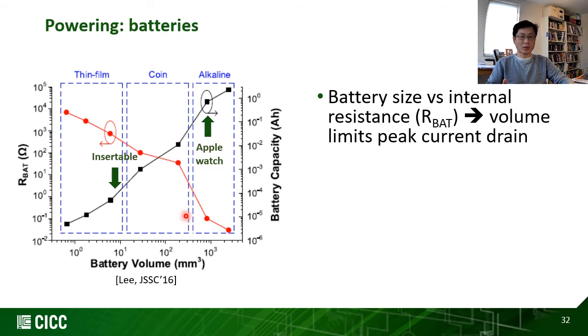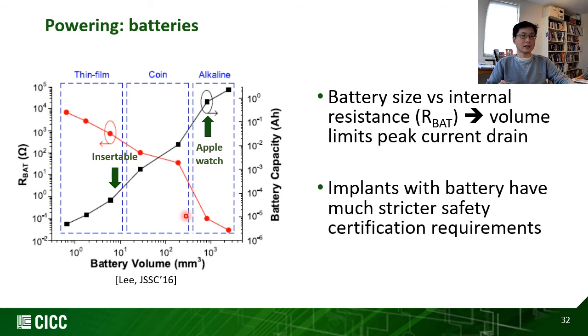For insertable implants, they only have a few cubic millimeters of volume and a capacity much lower than 1 milliamp hour. At the same time, their internal resistance is typically tens to hundreds of ohms. This means if you have large peak current draining, it creates a very large voltage drop, increasing the burden on power management units. In addition, if the implant has a battery, this automatically increases certification requirements, because batteries typically have chemical components that can lead to potential leaks. A rechargeable battery also has potential heating problems.